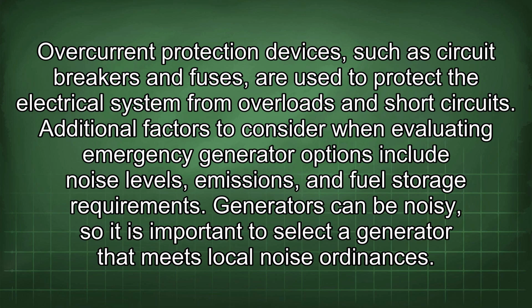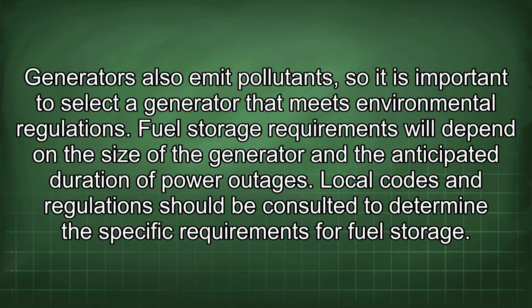Additional factors to consider when evaluating emergency generator options include noise levels, emissions, and fuel storage requirements. Generators can be noisy, so it is important to select a generator that meets local noise ordinances. Generators also emit pollutants, so it is important to select a generator that meets environmental regulations. Fuel storage requirements will depend on the size of the generator and the anticipated duration of power outages. Local codes and regulations should be consulted to determine the specific requirements for fuel storage.